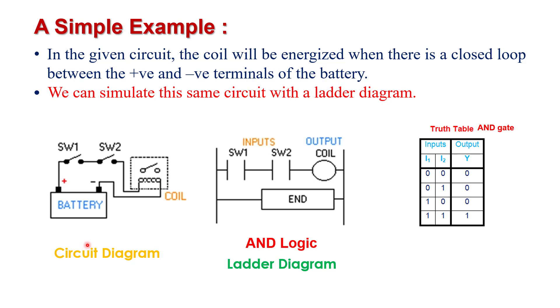Here we convert this electrical circuit diagram into a ladder logic diagram. Since the logic is AND gate logic, we use two vertical lines for power supply and one horizontal rung. Input is shown on the left-hand side and output is mapped on the right-hand side. Both switches are connected in series with the coil, because both are in series in the original circuit diagram. When both switches are closed, the output coil gets energized.